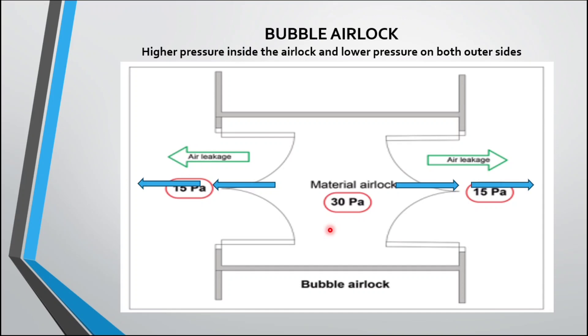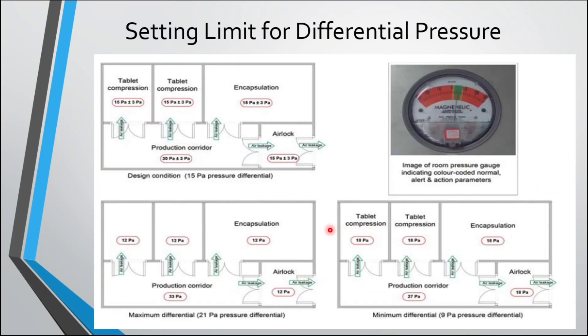The most important thing is to set the differential pressure correctly. In this figure, the area is designed so that the production corridor is at 30 Pascal and all surrounding areas are at 15 Pascal. That means 15 ± 3 Pascal is the limit for the surrounding areas, and 30 ± 3 Pascal is the limit for the production corridor.